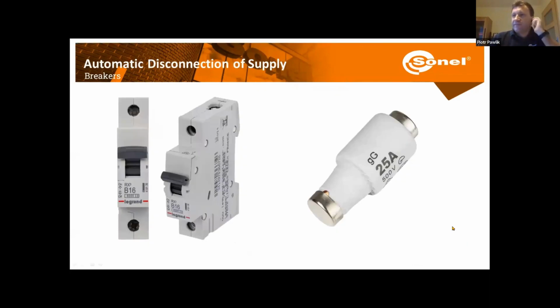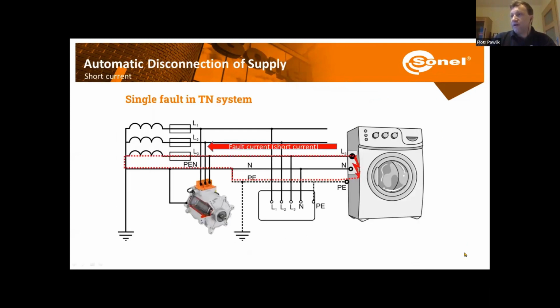Okay, here we have some examples. These are some older breakers. Right now we have automatic ones. Okay, so we know right now what is the level of the current that triggers our MCB or RCD or other breaker. But what do we need to make it actually trigger? Well, then the fault current flowing here in this circuit has to be higher than the current triggering our breaker.